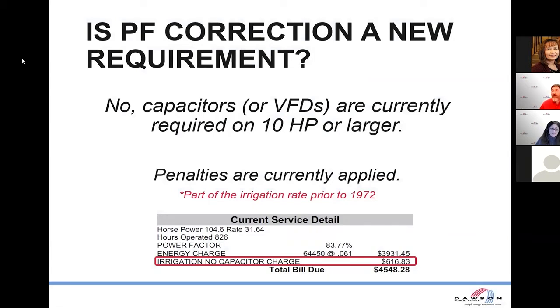So to start off, power factor, is this a new requirement? No, actually, since about 1972 at least, we were able to find in the records, capacitors have been required on all motors of 10 horsepower or larger. Recently, people have been using VFDs also to meet that requirement, so we waive the requirement for anyone that has a VFD since they're supposed to correct power factor as well.